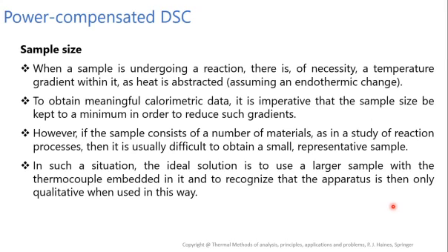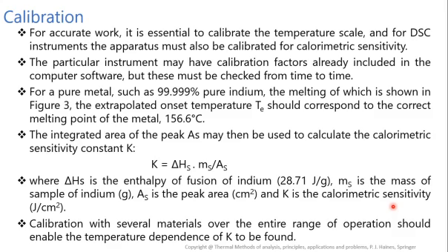However, if the sample consists of a number of materials, as in the study of reaction processes, then it is usually difficult to obtain a small representative sample. So in such a situation, the ideal solution is to use a large sample with the thermocouple embedded in it, and to recognize that the apparatus is only qualitative when used in this manner.